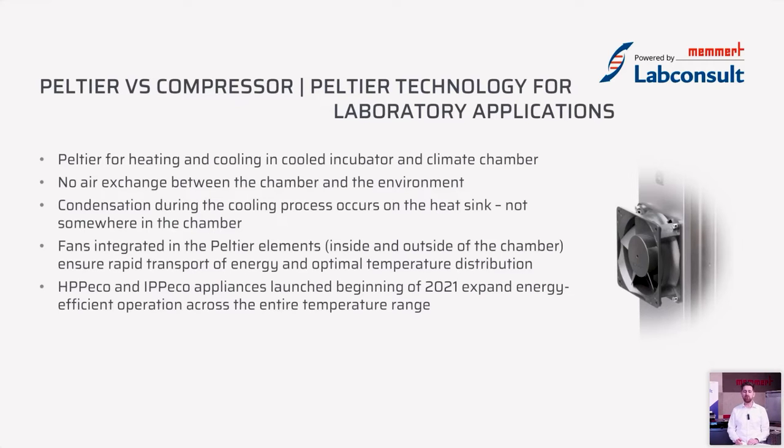If any condensation occurs during the cooling process, it occurs on the Peltier modules themselves and is guided outside of the chamber to avoid any contamination inside. Our HPPeco and IPPeco appliances were launched at the beginning of 2021, and since then we have had very energy-efficient operation with a great temperature range from 0°C up to 70°C.